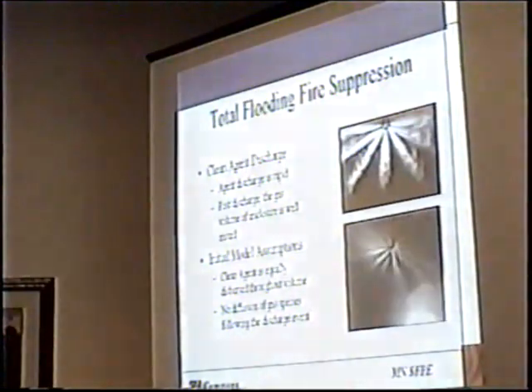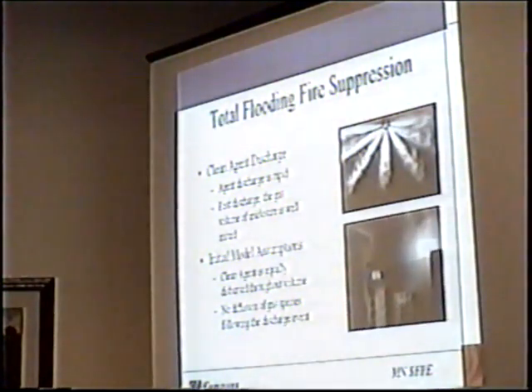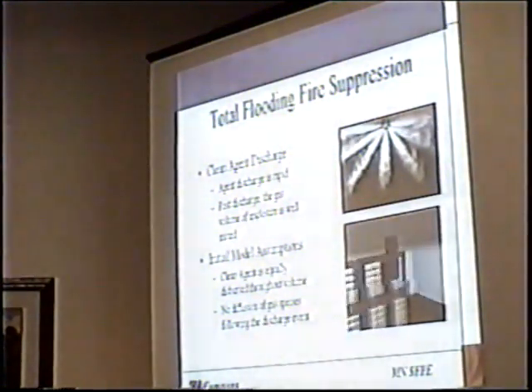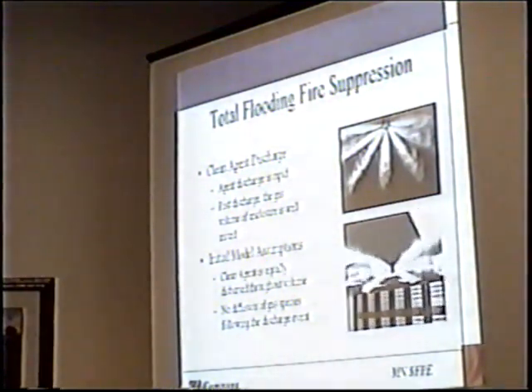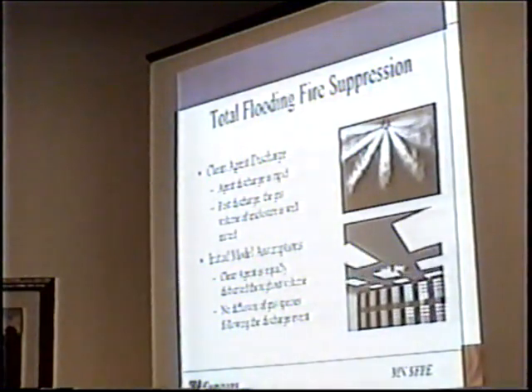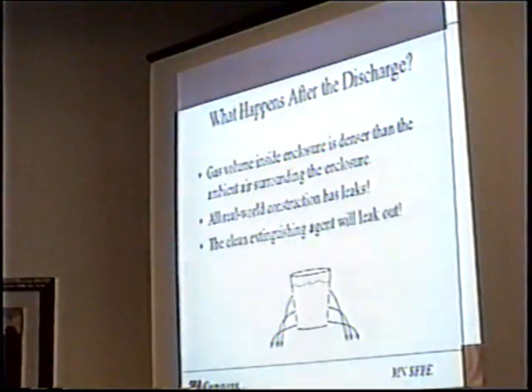So here, this is actually a Novec 1230 system. We've got a video of a discharge on the bottom. You can see that it's fairly turbulent, or at least aggressive for the most part. It's mixing well in the room as it gets in there. We're going to go ahead and make the first model assumption for the mathematics here and say that a homogeneous volume is formed. Thus, we don't have any agent settling to the bottom of the room. We've got an equal concentration throughout. We're also going to assume that there's no diffusion of gas species. It may seem a little over the top, but as we see, it actually works pretty well. So essentially what we're going to assume is that once the agent goes in there and fresh air comes in on top, there's just no mixing. There's a sharp interface that forms. Thus, we're going to call this model that we're building together here the sharp descending interface model.